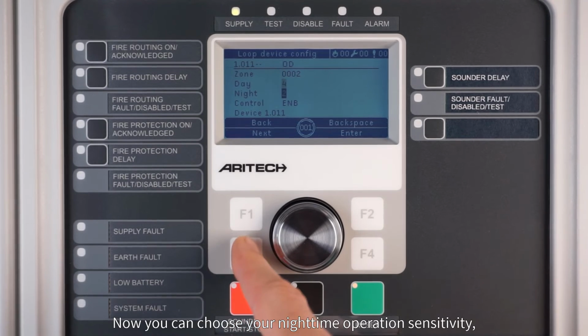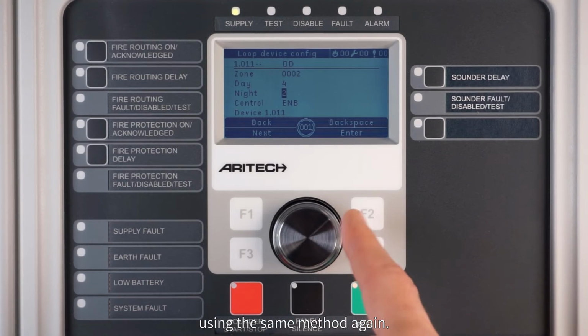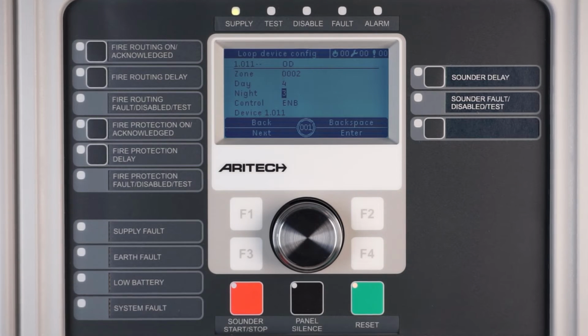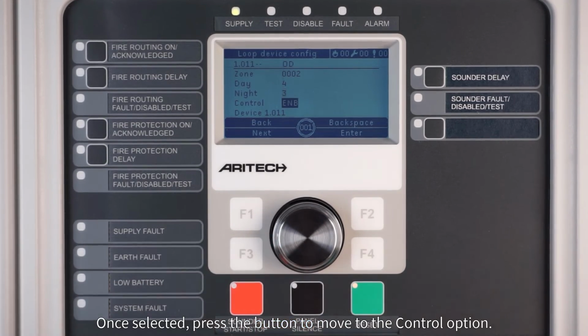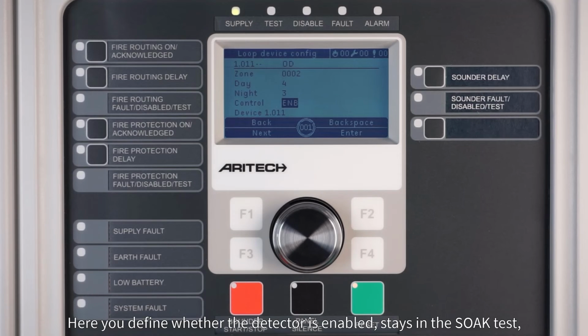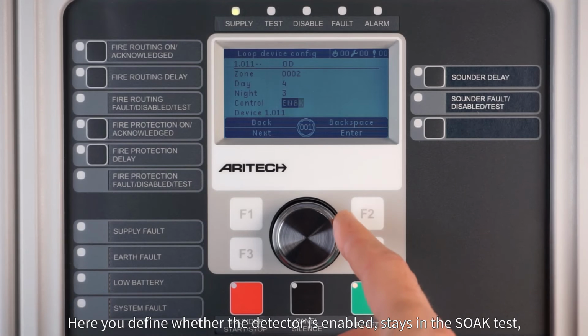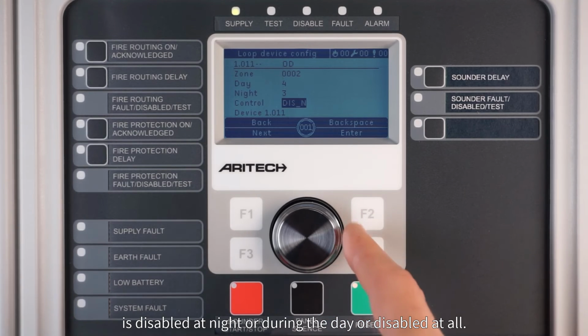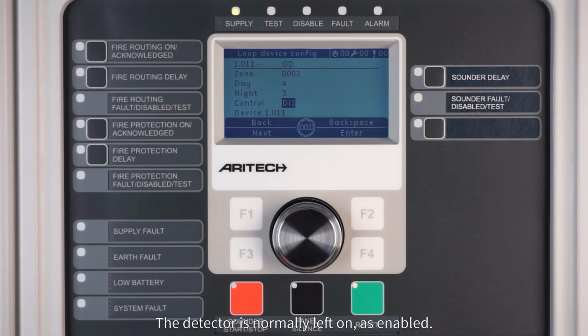Now you can choose your nighttime operation sensitivity, using the same method again. I will change it to level 3. Once selected, press the button to move to the control option. Here you define whether the detector is enabled, stays in the soak test, is disabled at night, or during the day, or disabled at all. The detector is normally left on, as enabled.